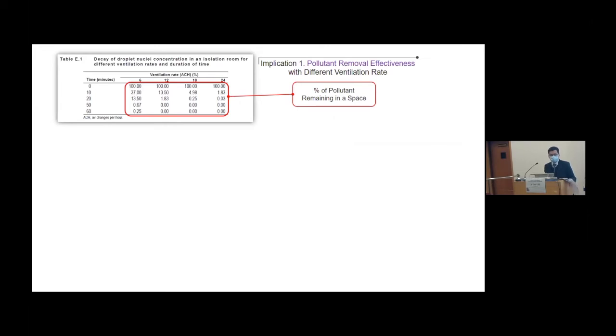The table you now see on the slide illustrates the calculated pollutant concentration decay with different ventilation rates in fully mixed isolation rooms. It assumes that the pollutant concentration in outdoor air is 0, and there is no source in the enclosed space, according to the simple concentration decay equation. So what this means is that we assume a room is initially full of pollutants. As you will see, the percentage of pollutants at time 0 is 100%, and with the different ventilation rates stated in ACH, the pollutants are being extracted from the room.